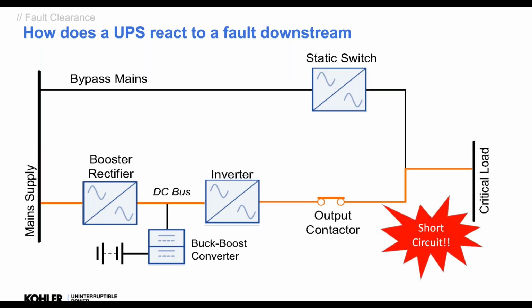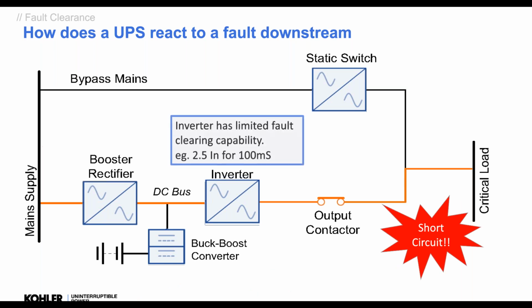Okay, so the UPS sees a short circuit, and it has a couple of different capabilities. The inverter itself is very limited. We're making the voltage up using transistors, IGBTs, so we might have a capability of 2.5 times the nominal current for maybe 100 milliseconds. Different manufacturers, different models will have different capabilities. It tends to vary from 2 times In to 3 times In for around 40 to a couple of hundred milliseconds. Okay, but it's not defined. It's something that you have to check with each UPS model.